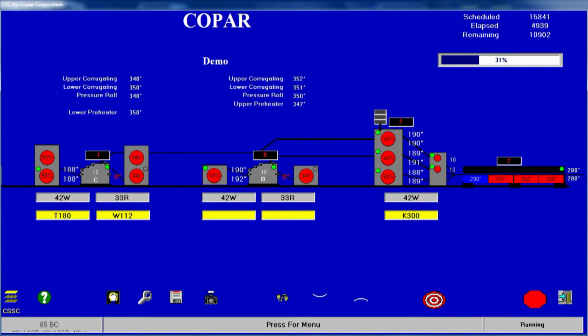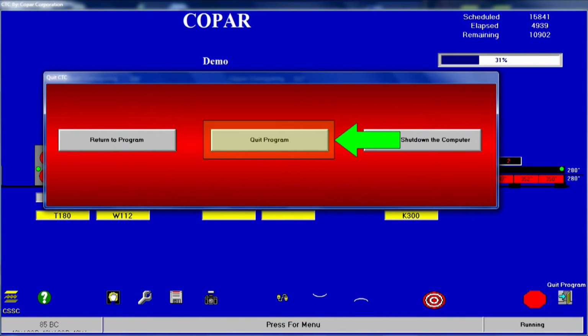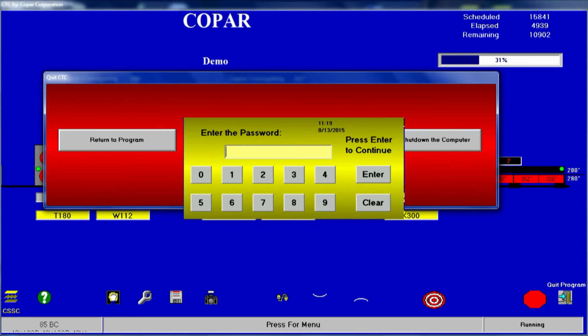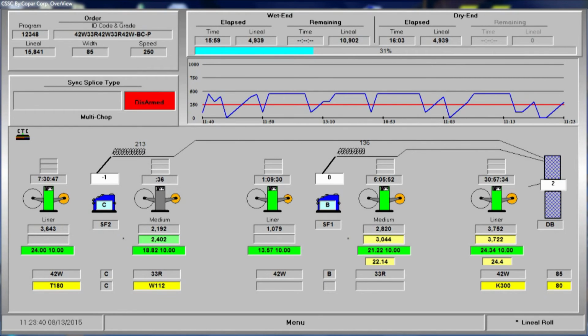In order to complete the change, we need to restart the CTC application on each Copar computer. Press the icon in the lower right corner to exit the program. Press the Quit Program button and enter the maintenance password. Once the program has shut down, press the CTC icon to restart the software.